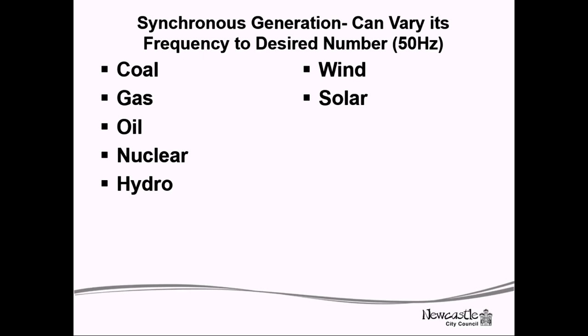We've got wind and solar - they're useful, but they can't play this role. 30 years ago, if a lot of our power was coal, you could have 90% of your stations able to black start. A black start enabled generator is one that can start itself with no external power input - basically, a diesel generator starts and powers up another generator, which powers up the main one, and that gets going. Because wind needs power in itself to work as an inverter generator, it cannot do that. So you'll be black starting with coal, gas, oil, or hydro - not nuclear, wind, or solar - trying to power up the network initially with around 60%.